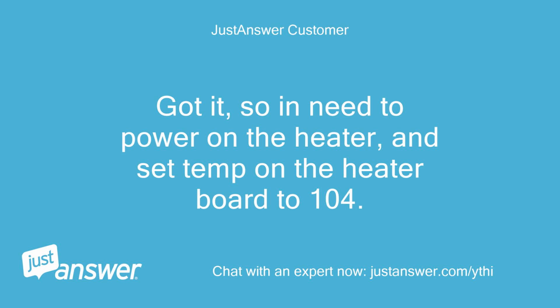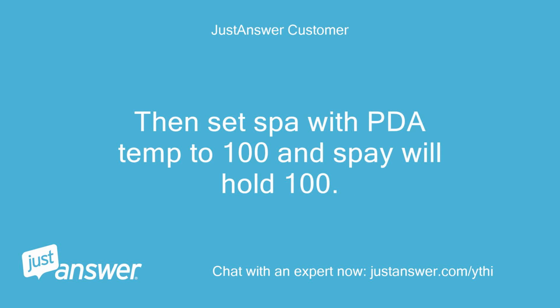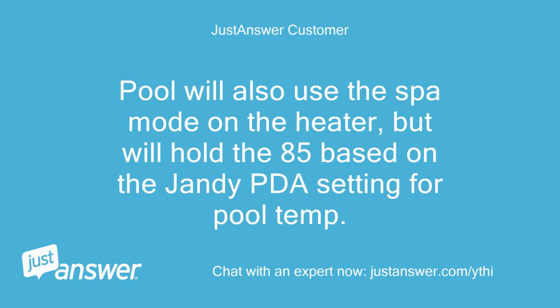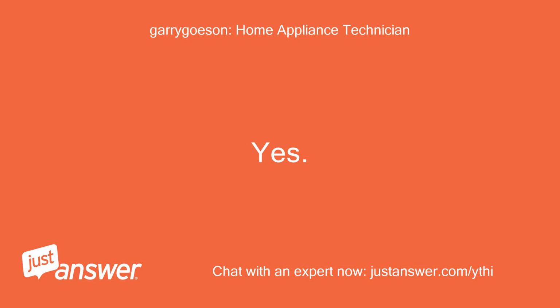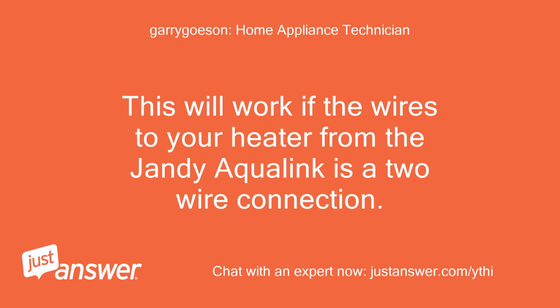Got it, so I need to power on the heater, and set temp on the heater board to 104. Then set spa with PDA temp to 100 and spa will hold 100. Pool will also use the spa mode on the heater, but will hold the 85 based on the Jandy PDA setting for pool temp. Yes. This will work if the wires to your heater from the Jandy Aqualink is a 2-wire connection.